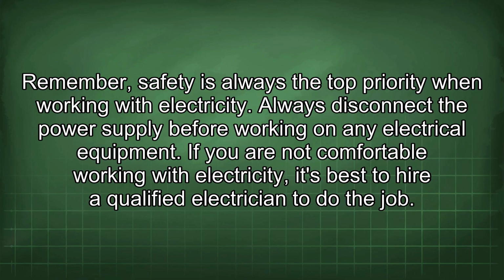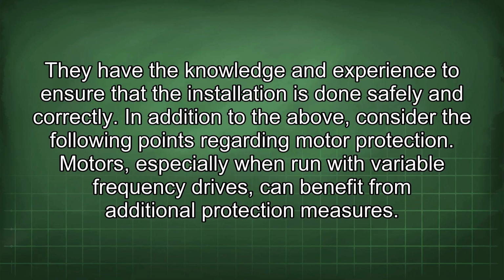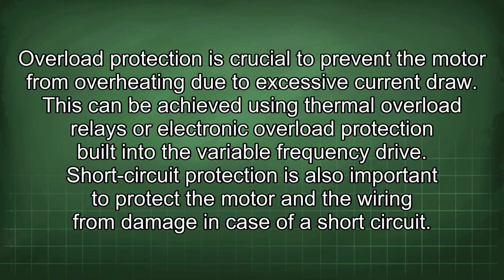Always disconnect the power supply before working on any electrical equipment. If you are not comfortable working with electricity, it's best to hire a qualified electrician to do the job. They have the knowledge and experience to ensure that the installation is done safely and correctly. In addition to the above, consider the following points regarding motor protection. Motors, especially when run with variable frequency drives, can benefit from additional protection measures. Overload protection is crucial to prevent the motor from overheating due to excessive current draw. This can be achieved using thermal overload relays or electronic overload protection built into the variable frequency drive.